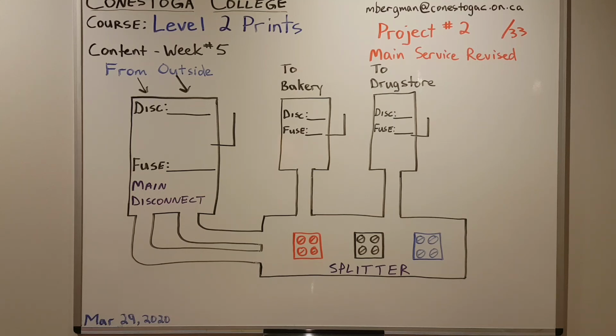I don't need the size of the disconnect on the secondary, and I don't need the size of the panel. Those will all be consistent with what the prints currently tell you, because they're already set up for 120/208. I want the 600 volt side of things. You're going to have to size the transformers, and we'll do some examples of those shortly.